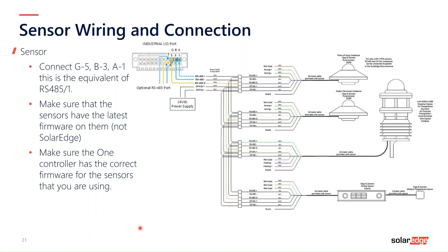We are limited to one thing currently: we can only show 10 devices on the monitoring portal, so 10 sensors. But don't be alarmed, because you can get sensors that cover ambient temperature, irradiance, wind, and module temperature all on one sensor, so you don't need to buy 4 different sensors. You can have visibility of 10, but up to 20 connected. Again, you don't need more than one sensor that does multiple functions. So if you need northeast/southwest coverage, literally 4 sensors is what you need.